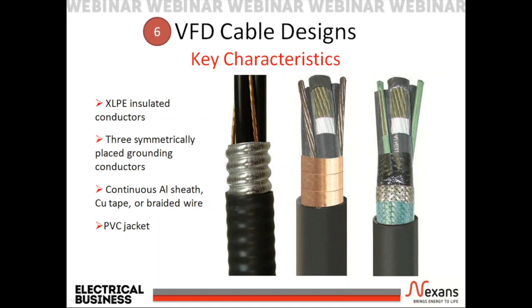The grounding conductors plus the aluminum sheath, copper tape, or braided wire provide a balanced, low frequency range, low resistance path to ground, virtually eliminating bearing currents and the electrical shock hazard. A continuous aluminum sheath, copper tape, or braided wire provides a shield for high frequency electrical noise, preventing interference with data and control signals, and provides a low impedance, high frequency bond path. A PVC jacket or other non-metallic jacket ensures grounding at cable ends only, eliminating ground loops and resulting in no injected ground current, and protects the cable from the installation environment.